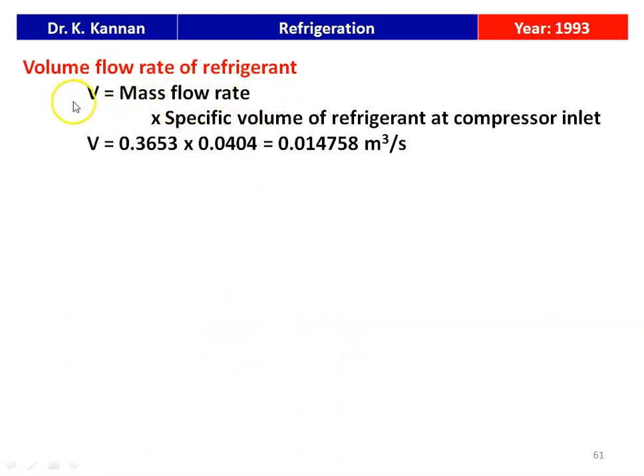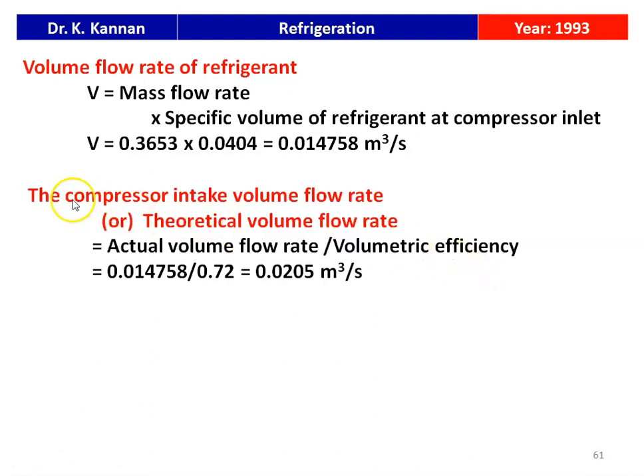The volume flow rate of the refrigerant = mass flow rate × specific volume at compressor inlet = 0.3653 × 0.0404 = 0.014758 m³/s. The compressor intake volume flow rate (theoretical) = actual volume flow rate / volumetric efficiency = 0.014758 / 0.72 = 0.0205 m³/s. This is the answer to the problem.